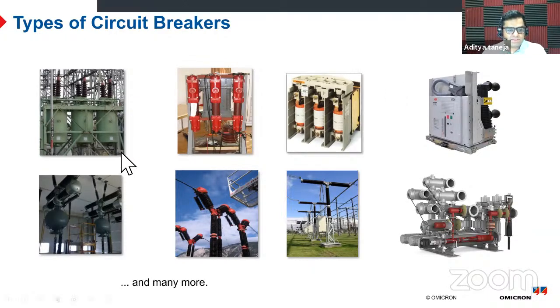What we see here is a glimpse of the variety in the market. On the very left, we have very old 1960 designs of dead tank oil circuit breakers. These tanks were filled with oil, which was used for cooling the arc and operating the breaker safely. Then we have the minimum oil design, which was an improvement on this one. Then we have vacuum ones, and then air, again a very old design.